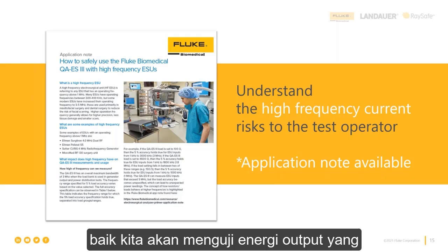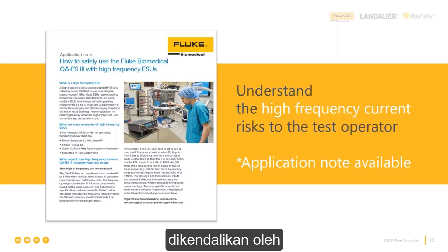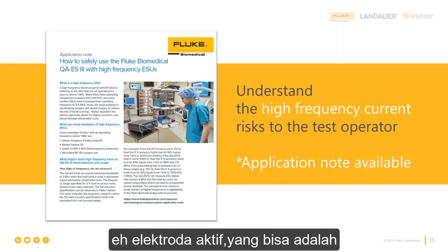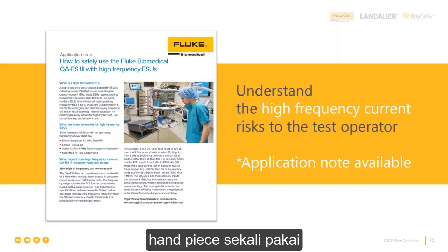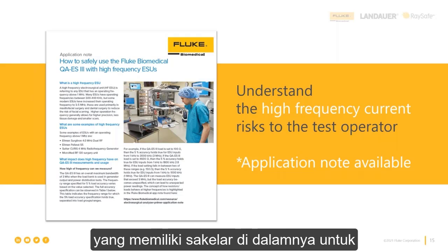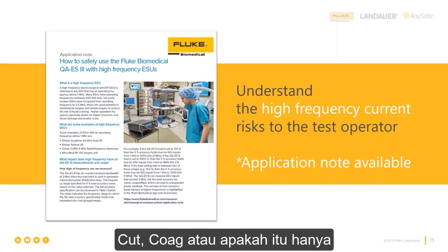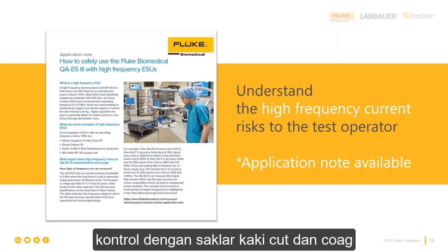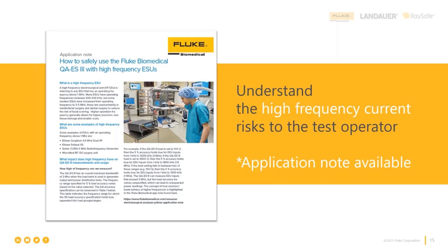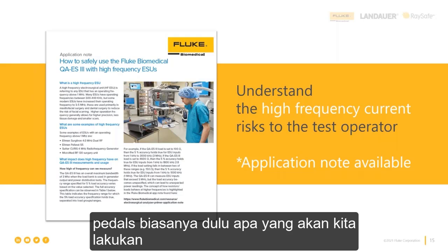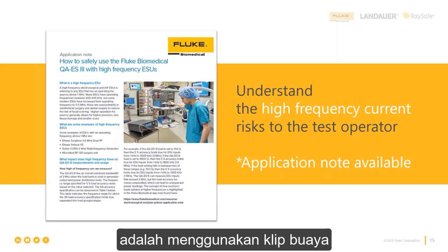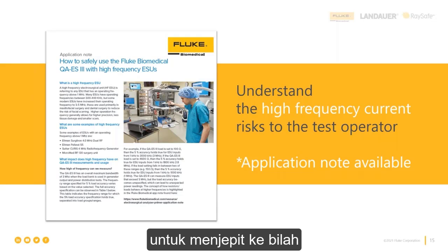And what do I mean by that? Well, we're going to test the output energy as controlled by the active electrode, whether that's a disposable handpiece that has a switch in it for cut and coag, or whether it's just the active electrode that we're going to control by the foot switch cut and coag pedals. Usually in the old days, what we would do is use an alligator clip to clip onto the blade of that active electrode. Yeah, not so safe.